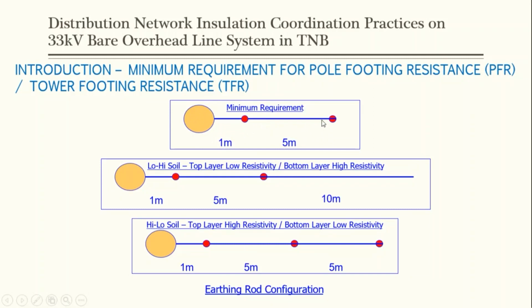Okay. But what if we have a low-high soil, meaning that the top layer has a low resistivity, but the bottom layer has high resistivity. So the configuration would be from the pole, we have 1 meter distance to the first copper rod, another 5 meter to the next copper rod, and we lay the counterpoise earth tape 10 meters from the second point, right? But without any copper rod driven into the ground because the top layer already has low resistivity.